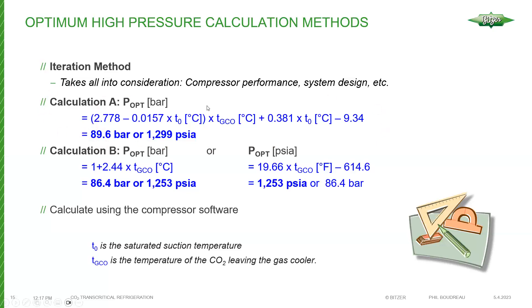There are also algorithms used. Calculation A uses an evaporating temperature and gas cooler outlet temperature to determine optimum pressure. There's another somewhat more simplified calculation — a metric version and an IP version — to determine the high-side pressure. If you look at the difference between the two, approximately 1250 versus 1300 PSI, the difference in COP at that point is only about 0.01, so 50 PSI is really not that significant.